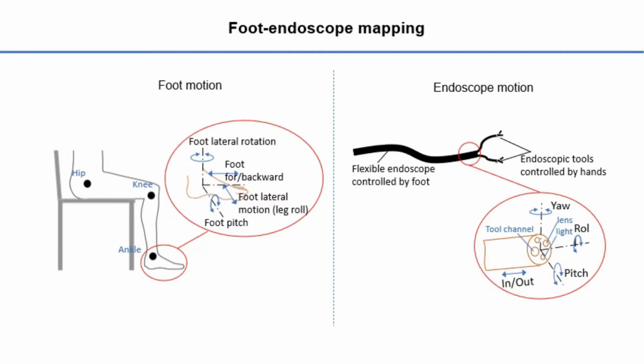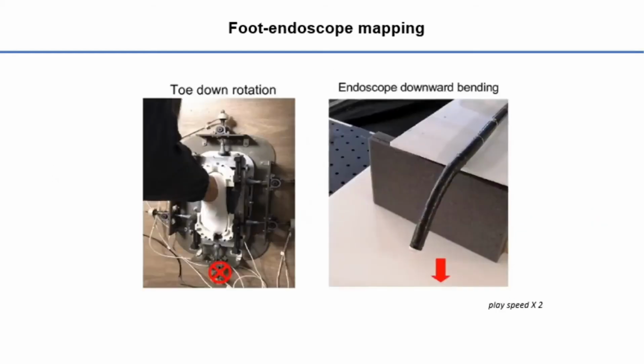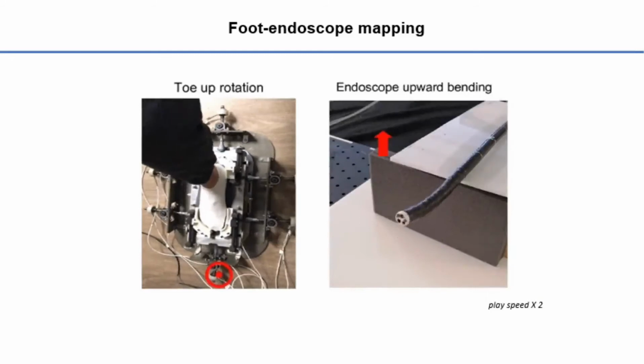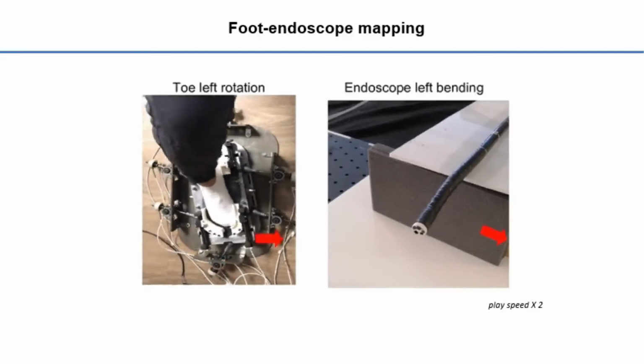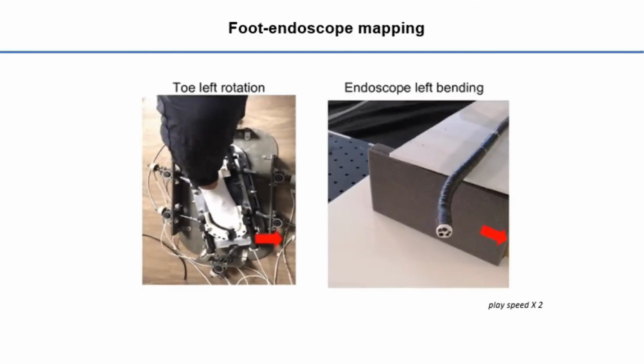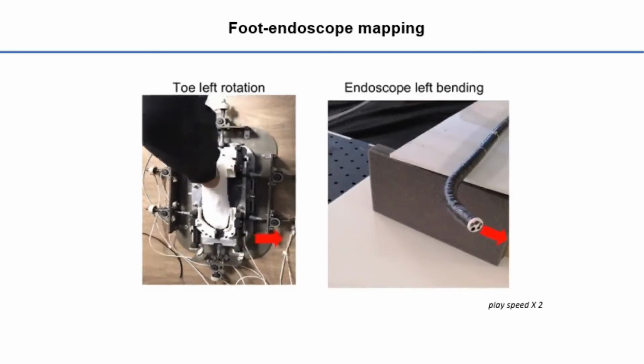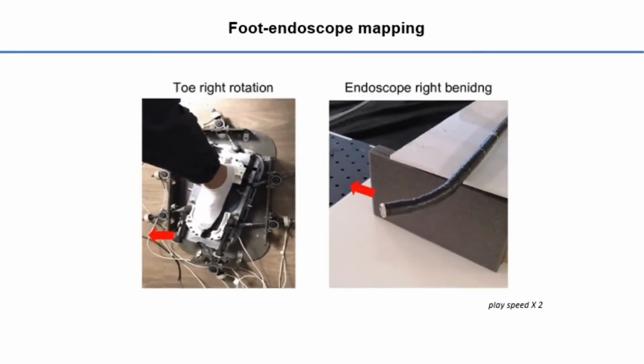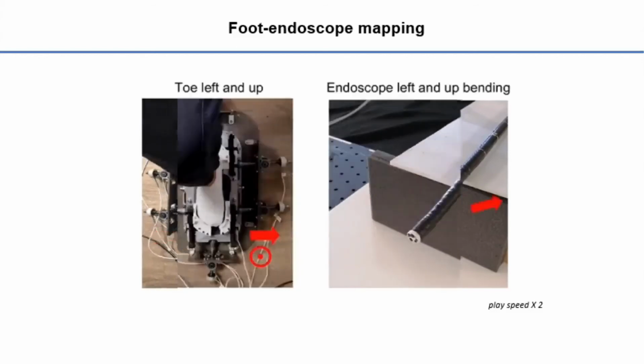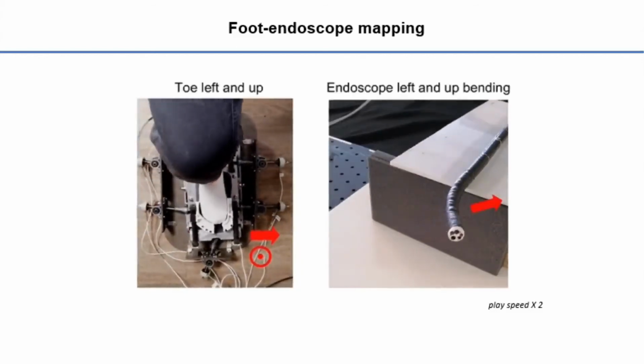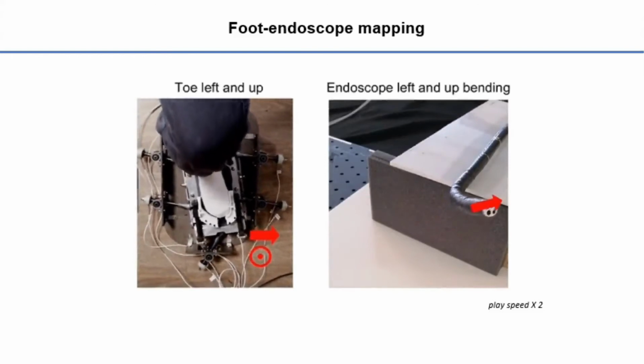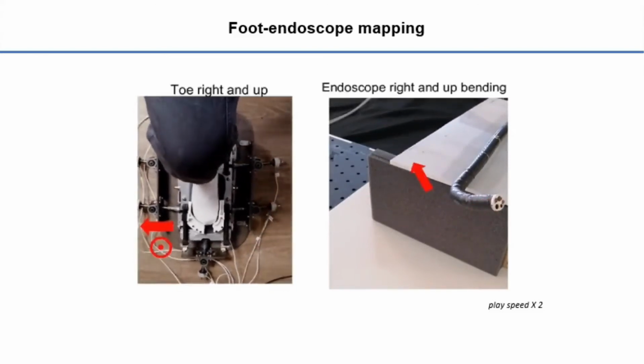The operator can just imagine their toes as the tip of the endoscope and remote control the slave end effector intuitively through isomorphic mapping. Pressing and lifting the pedal, activated by toe up-down rotation, controls the up-down bending of the endoscope. The left-right rotation of the pedal is linked with the left-right bending of the endoscope. Bending in multiple degrees of freedom is allowed. For example, lifting and rotating left of the pedal could lead to up-left bending of the endoscope.